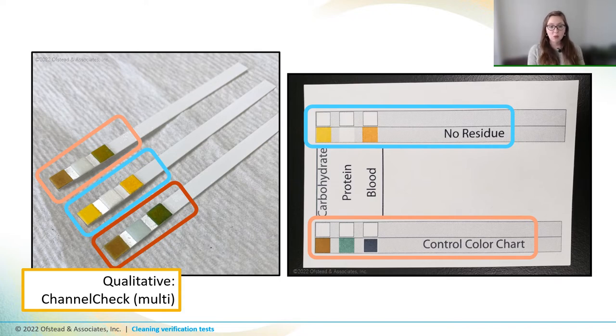Now, a scope where any pad turns colors should be re-cleaned because it's still dirty, even if it doesn't have all three types of soil present.